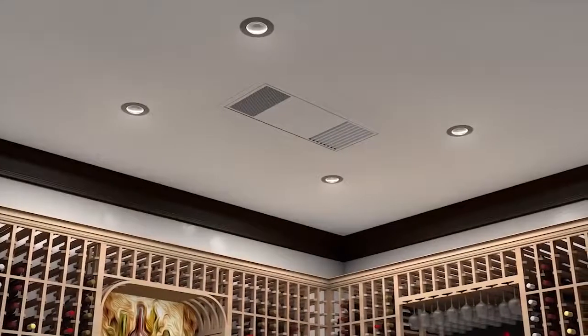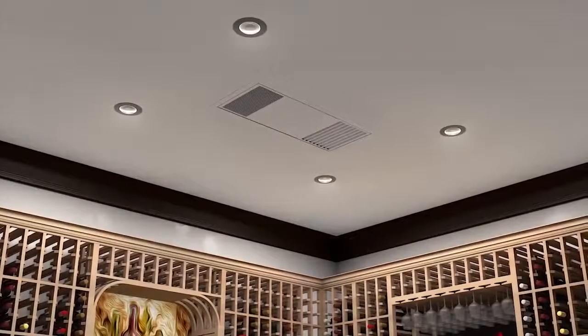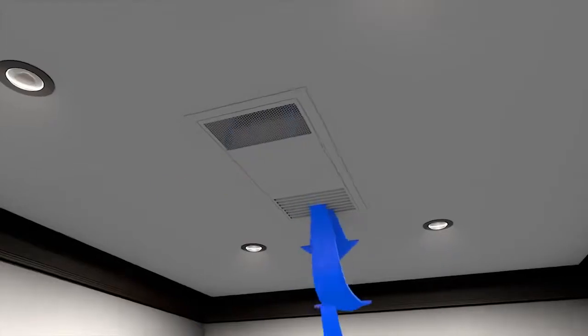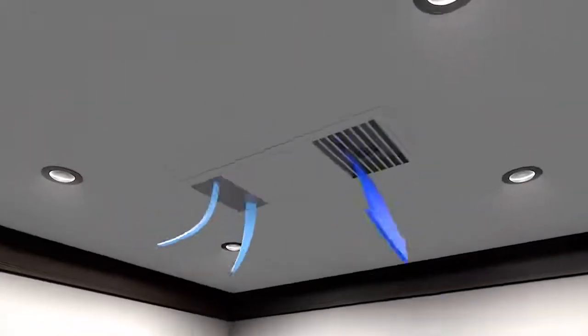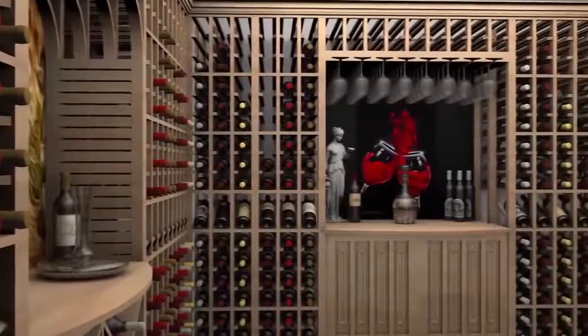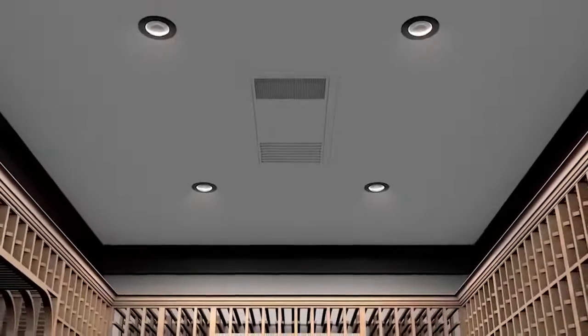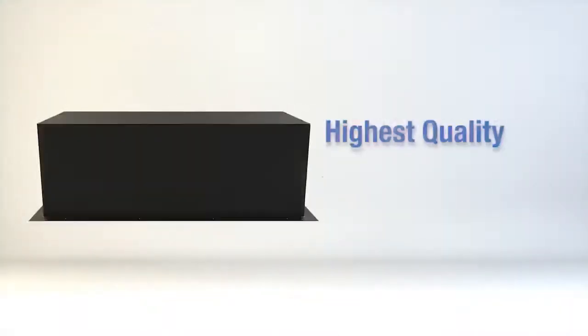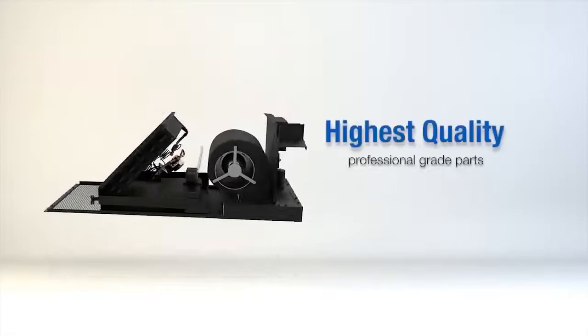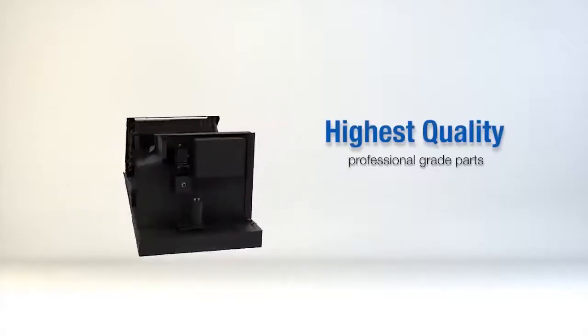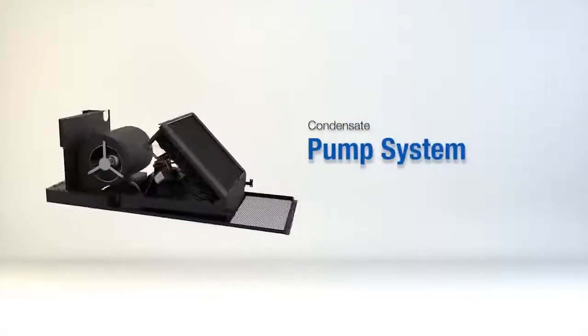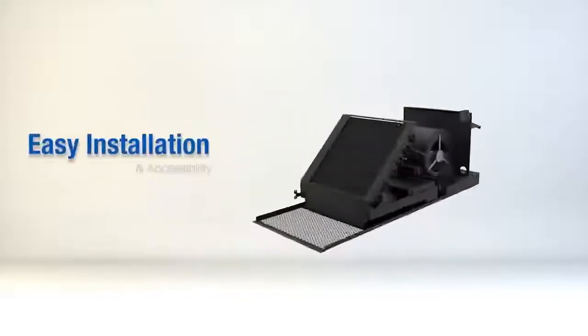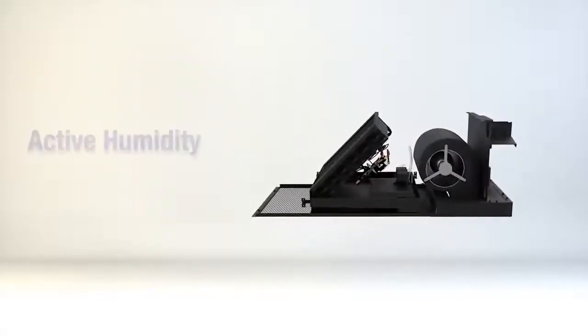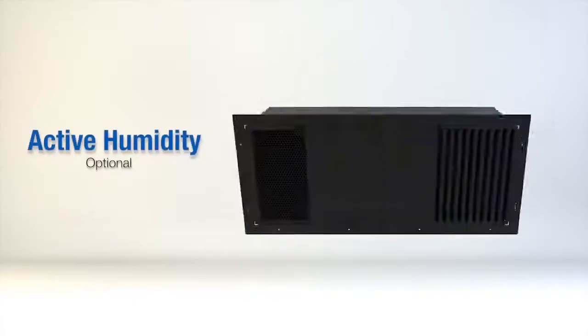Utilizing our ceiling mounted evaporator has many benefits. It offers excellent efficiency by drawing in the warmer air, which accumulates at the ceiling, cools and disperses the air throughout the environment. Allows for maximum racking space, is virtually invisible in the cellar. Designed with the highest quality, professional grade parts for longevity and performance. Includes a condensate pump system. Designed for ease of installation and accessibility. Available with our active humidity option.